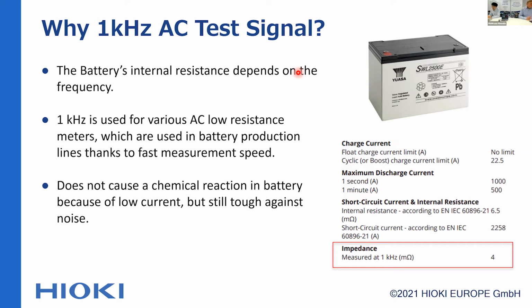However, the purpose of maintenance is to find the deteriorated battery in the UPS speedily. It is known that the internal resistance of the battery caused by battery degradation can be detected at the 1 kHz point. The 1 kHz signal method is faster than the DC resistance measurement method, and there is no discharge of the battery during the test because it uses a small test signal.